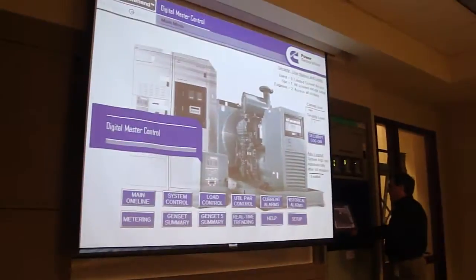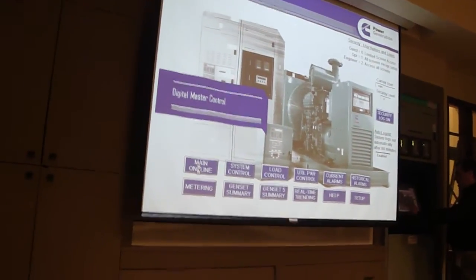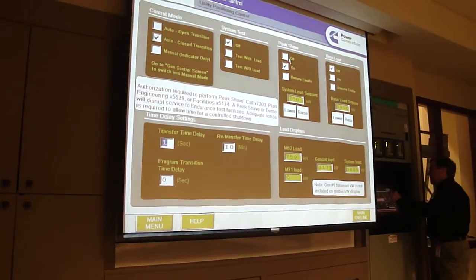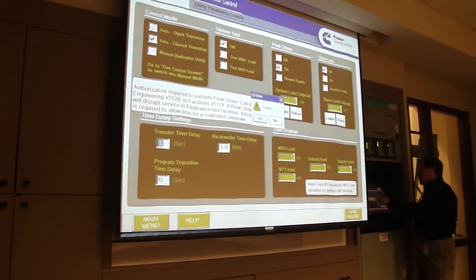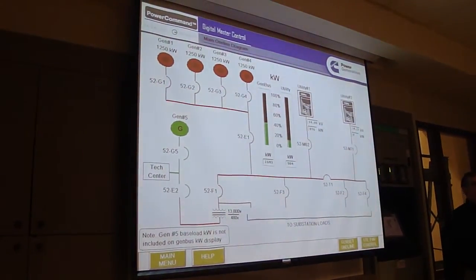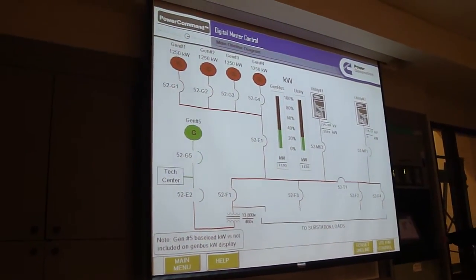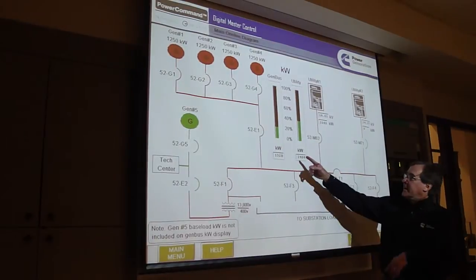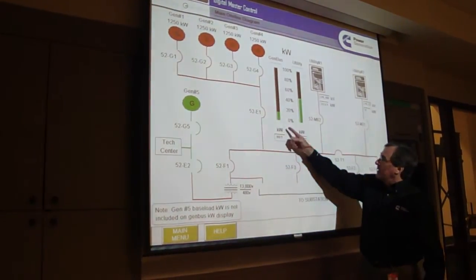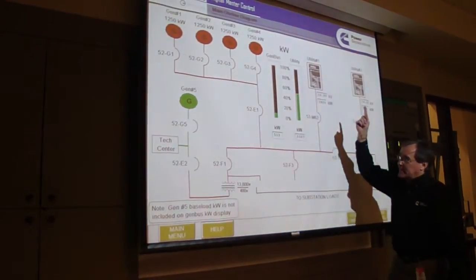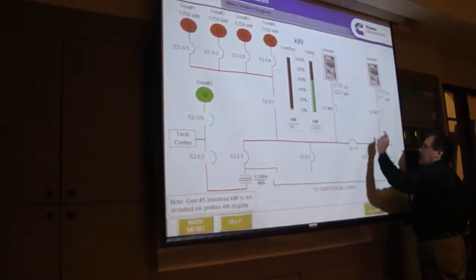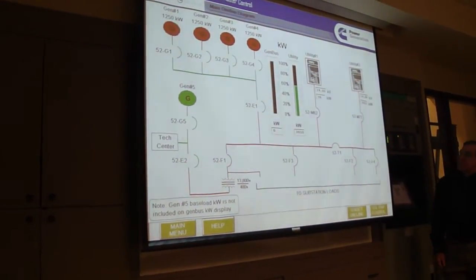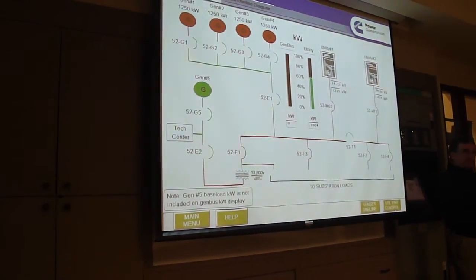I'm going to turn it off here and then go so you can watch that happen. The master control was put in about 10 to 12 years ago and has been upgraded once. Now it's ramping back as I told it — it's ramping back by backing off the fuel. When it gets to below 10%, it will open the breakers, transfer this back, close the breaker in the other room and open this one. And now they're just going to run and cool down for 10 minutes.